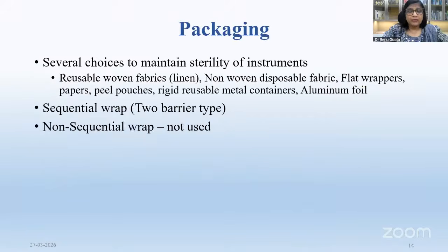After assembly, you have understood this, you have received items in your CSSD. First of all, you are cleaning, then you are inspecting whether they are working properly, whether they are actually clean, there is no blood spot. After that, you lay them down in your sterilization tray in a proper way according to the type of the surgery, according to the usage. Sometimes you know that this instrument will be required prior to the next instrument. Then the packaging.